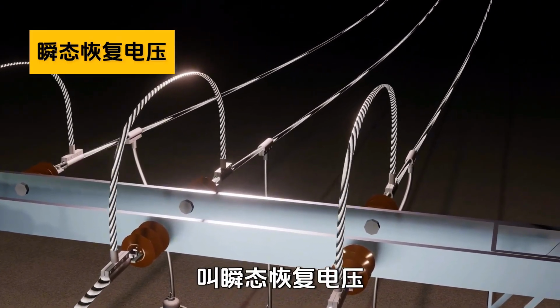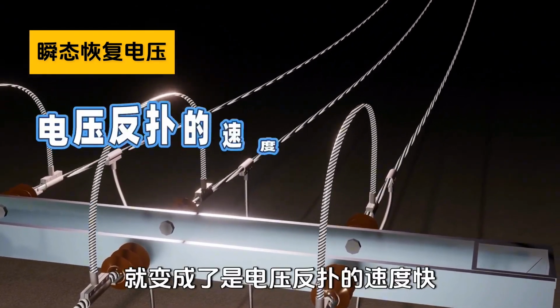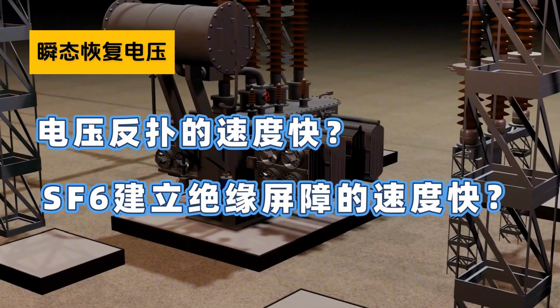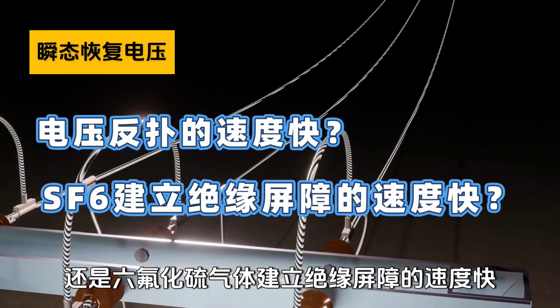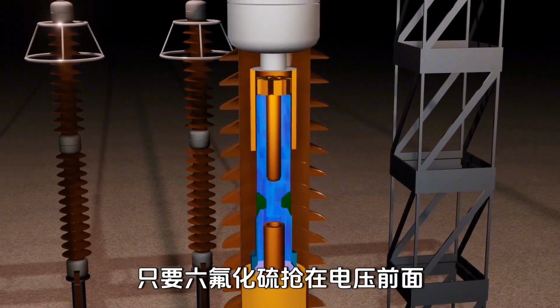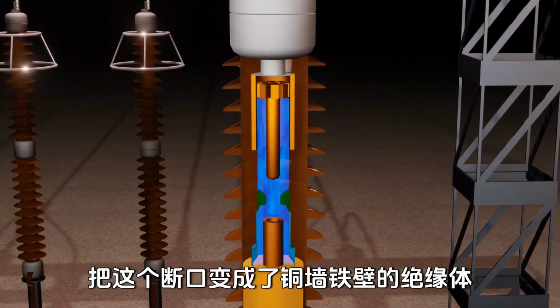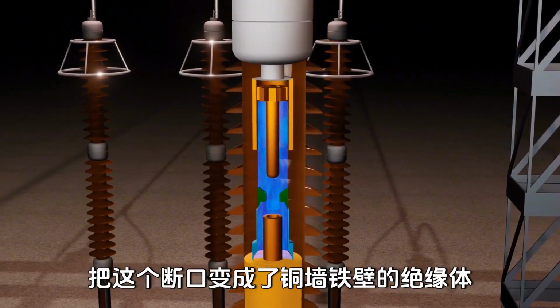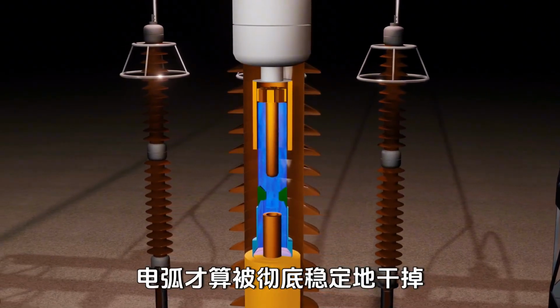Now it's a race. Which is faster? The returning voltage, or the SF6 gas building an insulating wall? If SF6 builds that insulation faster, it turns the gap into a solid wall of resistance. That's when we can finally say, the electric spark has been completely extinguished.